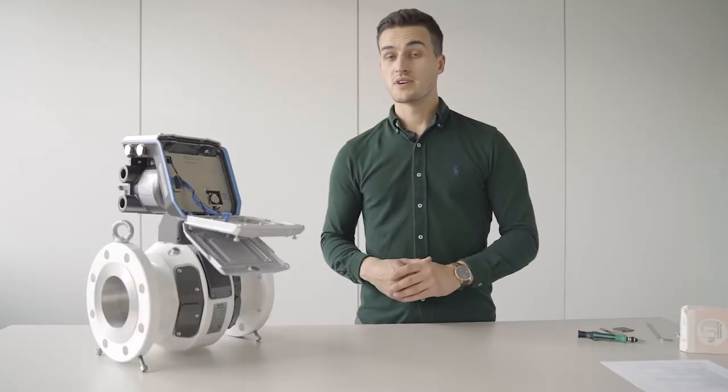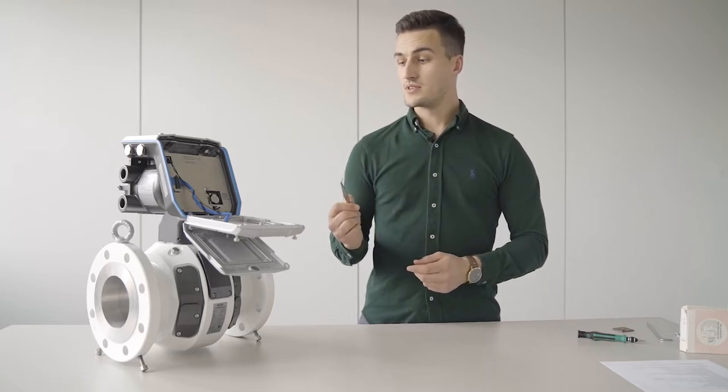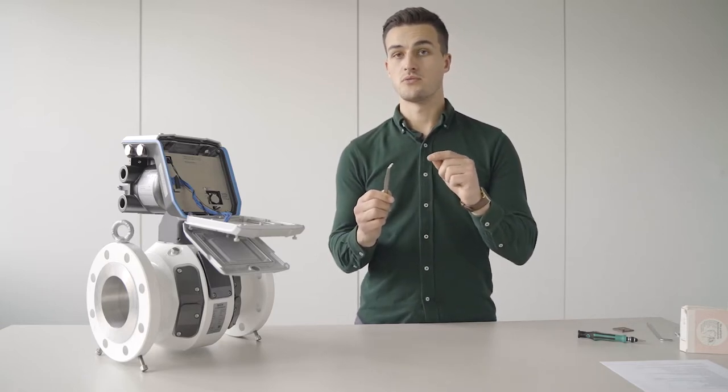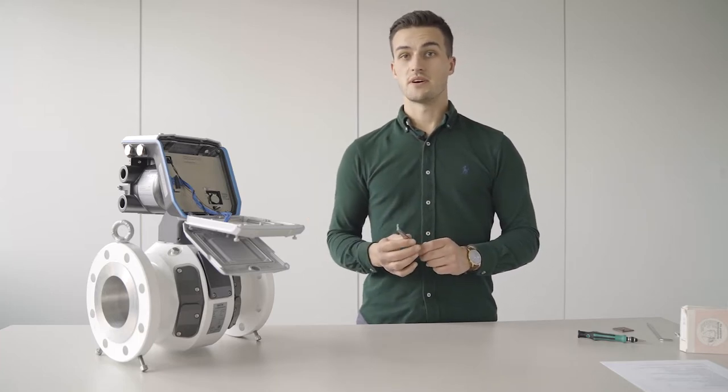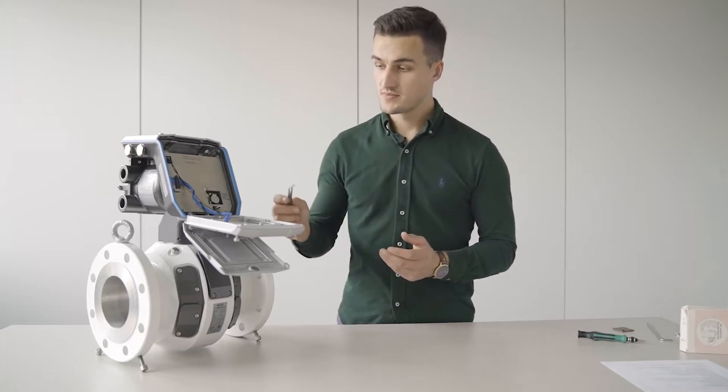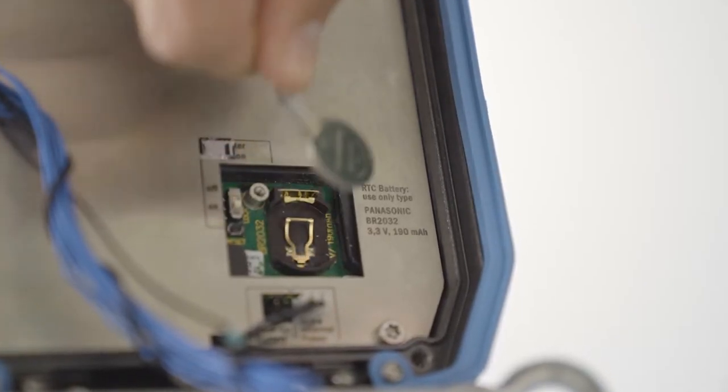After removing the protection flap, you will need a pair of tweezers. Please ensure that the tip of the tweezers is covered to prevent the RTC battery from any damages. So please carefully remove the RTC battery with the pair of tweezers.